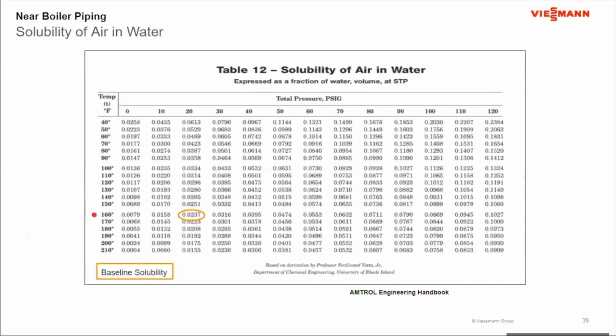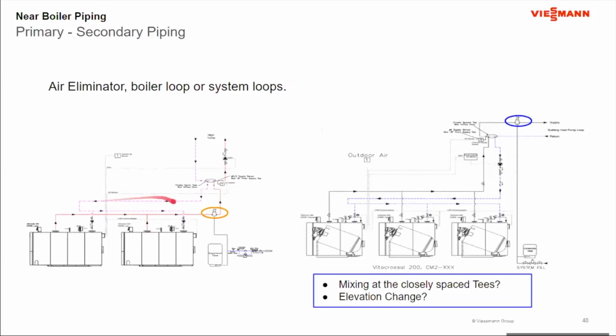For my example, I'm going to say the highest water temperature I'll see out of the boiler is 160 degrees. It could be 160, it could be 140, it could be 180. But at 160, and 20 psi, and 20 psi was a random number I chose, the solubility is 0.0237, or 2.37% of the system's volume can be dissolved air. That's my solubility, my saturation point, okay? Now, when I start to look at air separation, I want that air separator at the point where this number is going to be the lowest solubility, okay? So if I put this here, solubility is based on temperature and pressure.